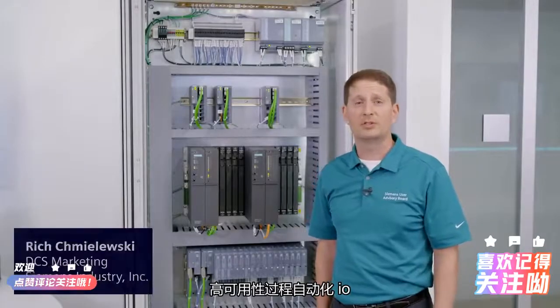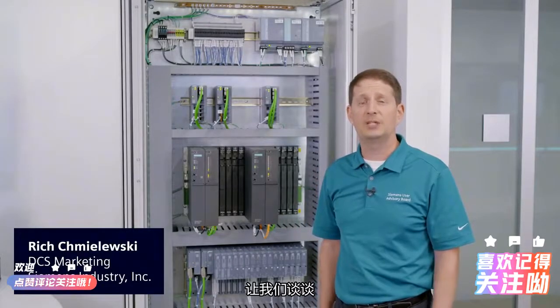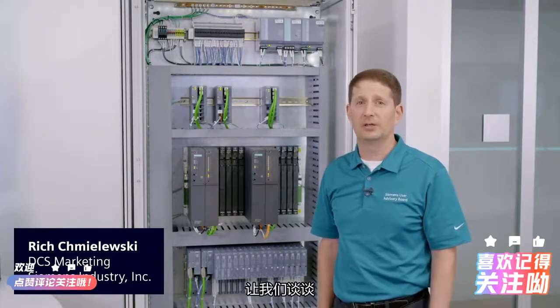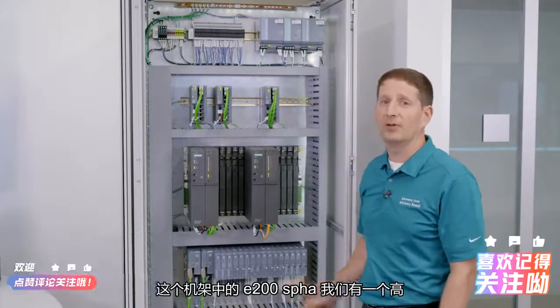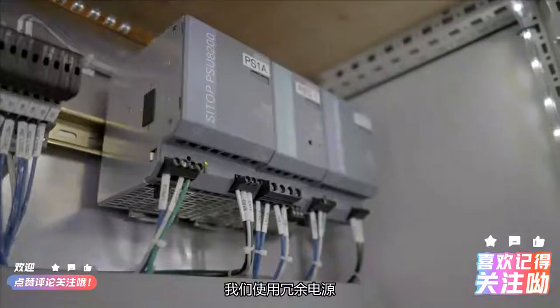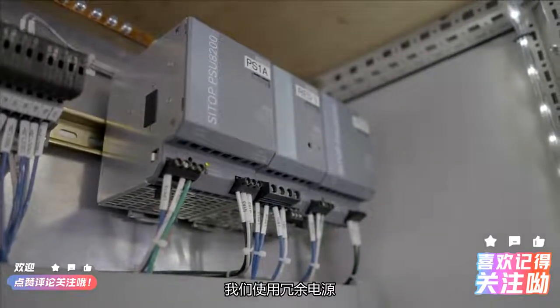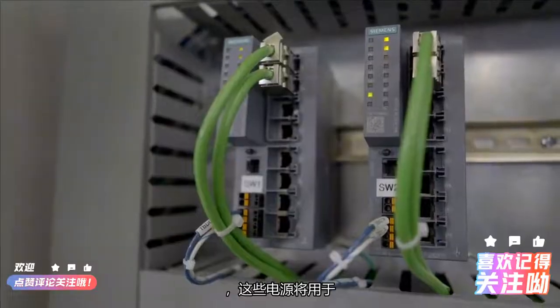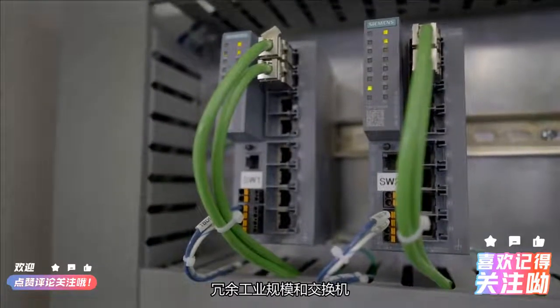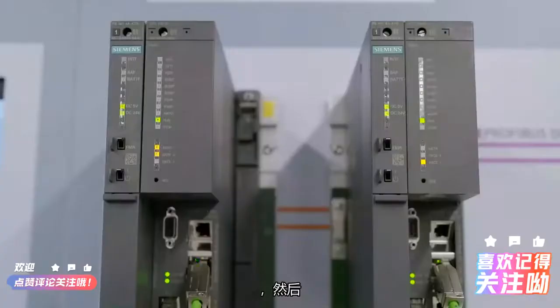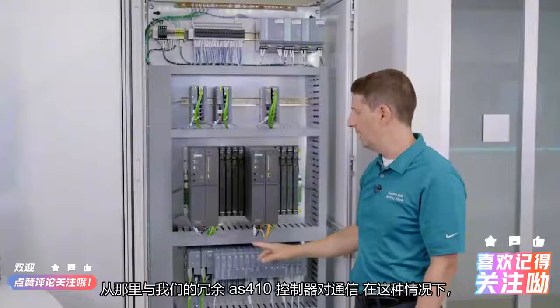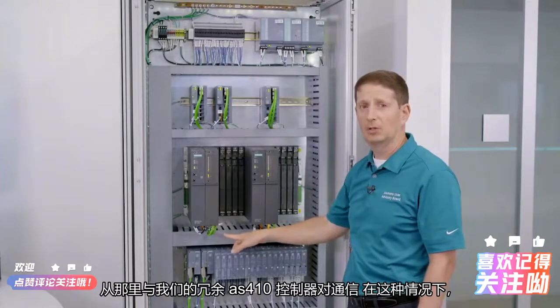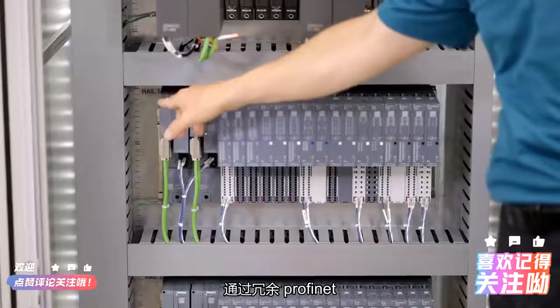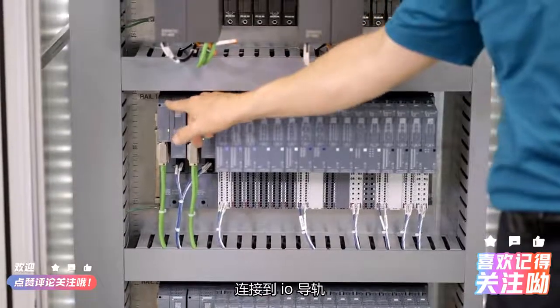High availability process automation I/O. Let's talk about ET200SP HA. In this rack here, we have a high availability architecture. We're using redundant power supplies, which are going to redundant industrial Ethernet switches, which then communicate to our redundant AS410 controller pair. From there, we're going out via redundant PROFINET to the I/O rail.